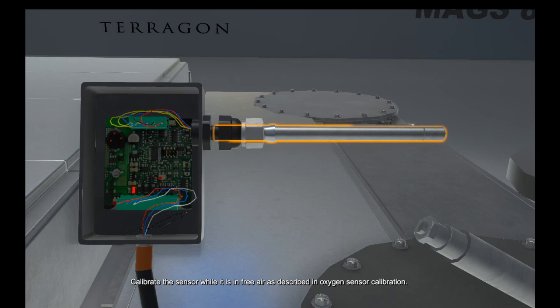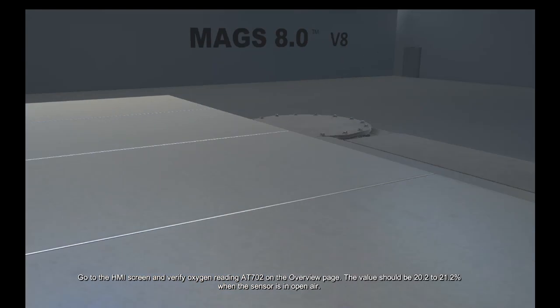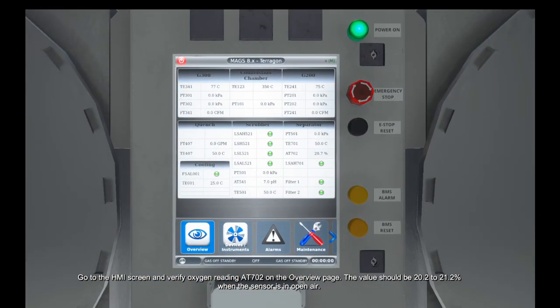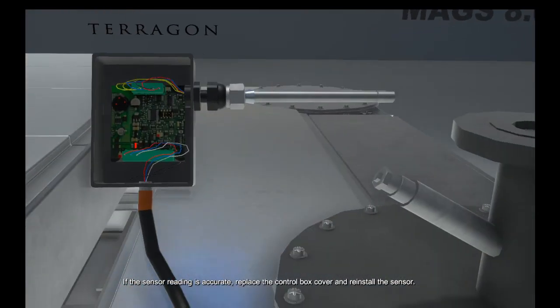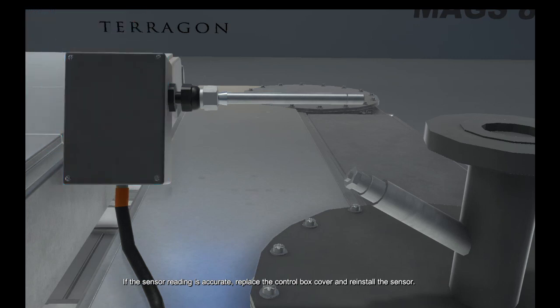Calibrate the sensor while it is in free air as described in oxygen sensor calibration. Go to the HMI screen and verify oxygen reading AT702 on the overview page. The value should be 20.2 to 21.2 when the sensor is in open air. If the sensor reading is accurate, replace the control box cover and reinstall the sensor.